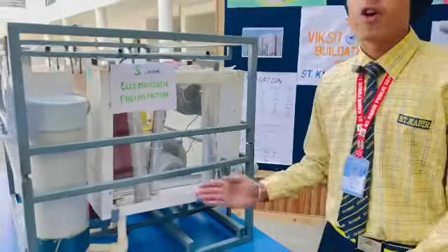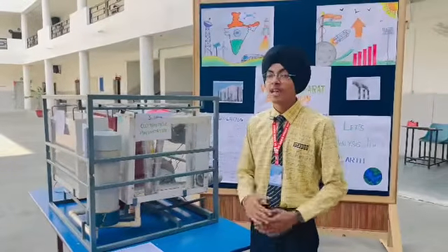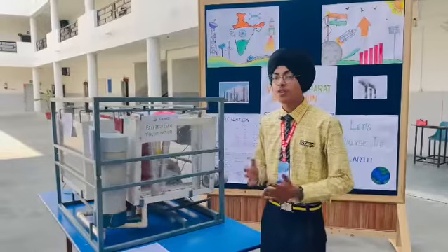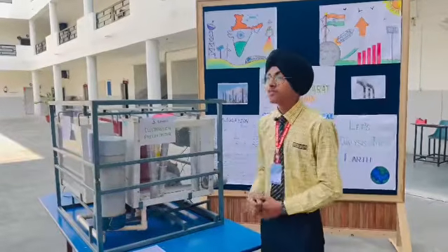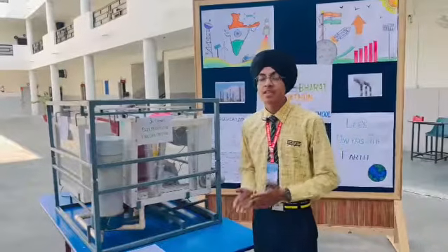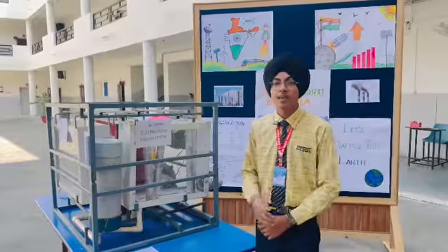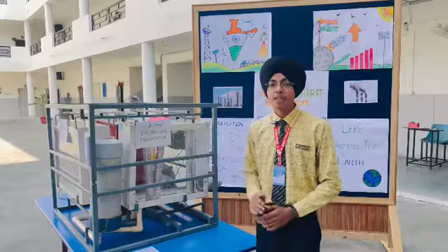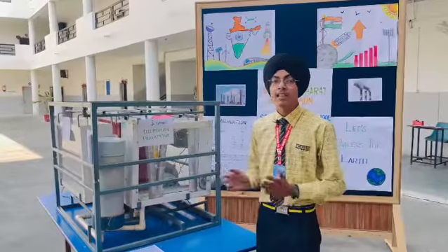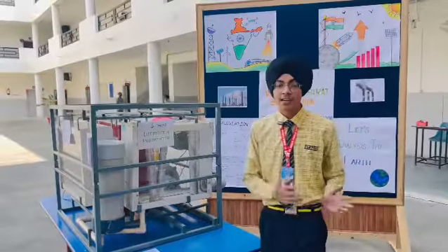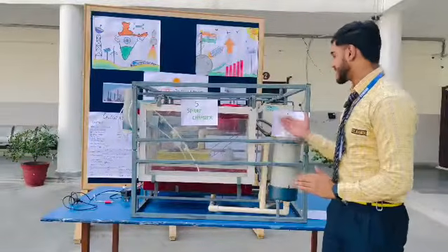The next section of our system is the electrostatic precipitator. In this part, we use several electrodes that maintain a constant voltage to create a potential difference. This potential difference will produce an electrostatic force which will help us to separate the nano-sized carbon particles from the industrial exhaust air. The positively charged particles get attracted towards the negative terminal and the negatively charged particles get attracted towards the positive terminal.